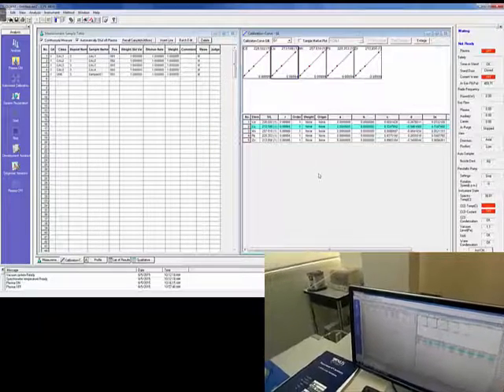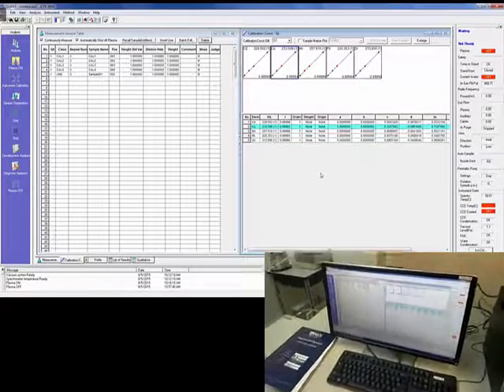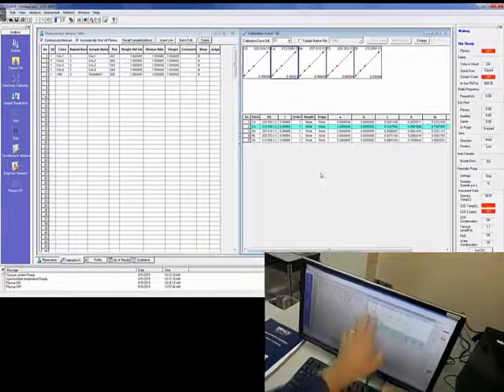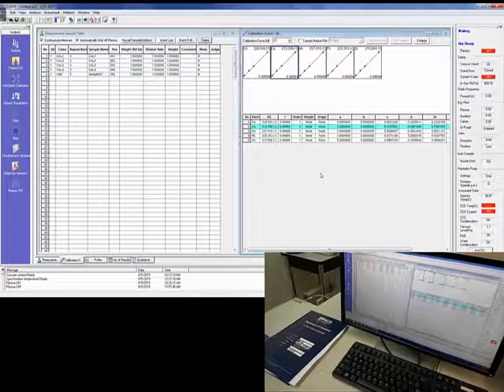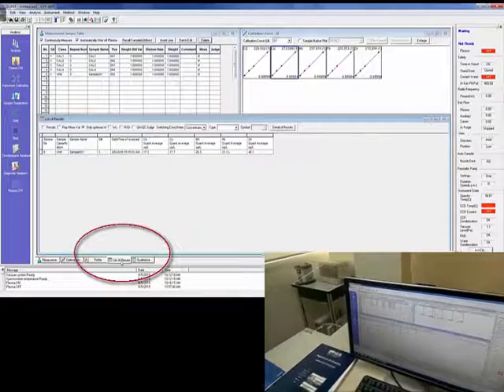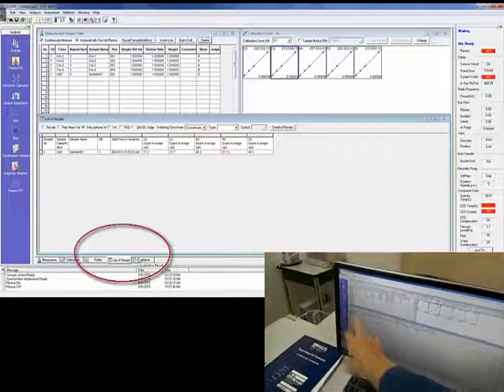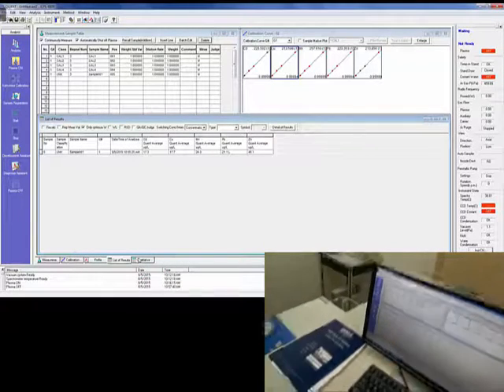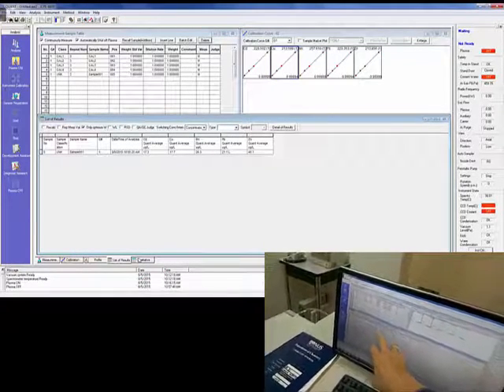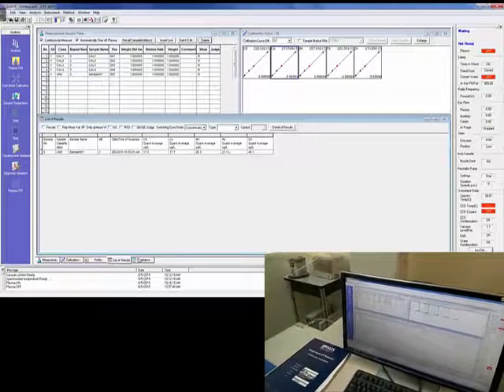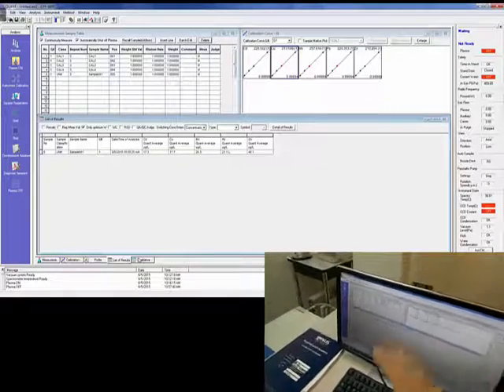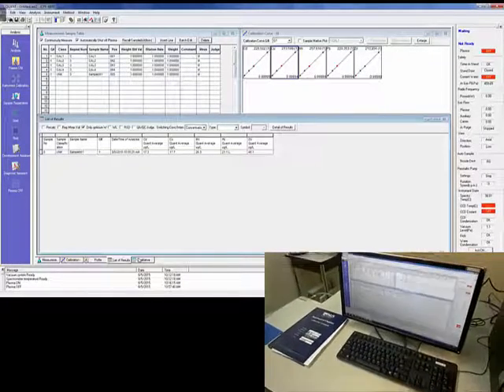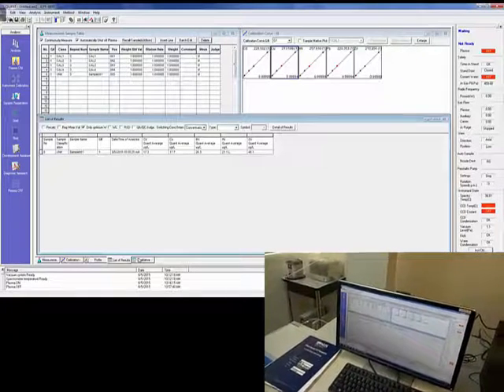Okay. The next part, what we have to do is, if we're happy with the data, we're happy with the calibration curves, we can then get the actual results. Now, click down there. In this case, we only had one sample and the results here in micrograms per liter, which is PPB, of the elements we analyzed for—which for zinc, lead, manganese, copper, and cadmium—are as here. Now, your sample table will be much bigger as you'll have very many samples, and therefore that will be larger.